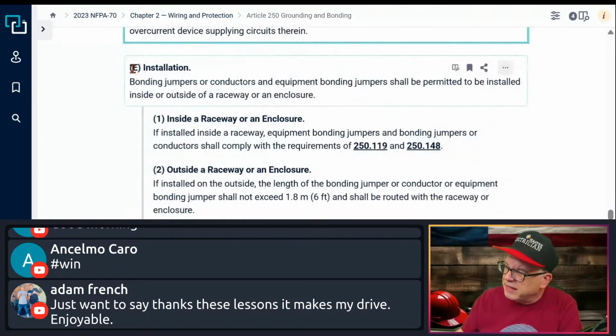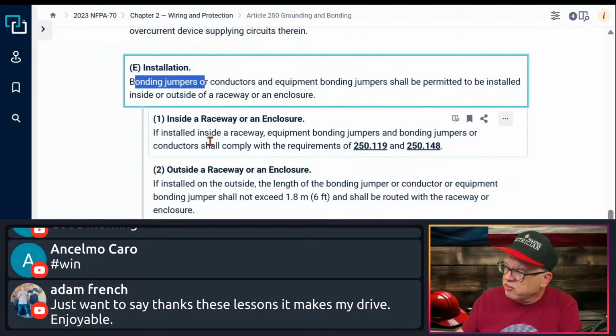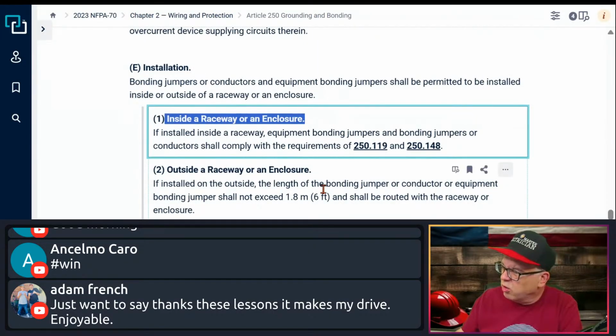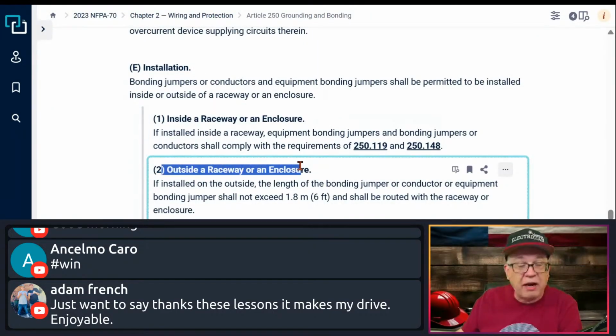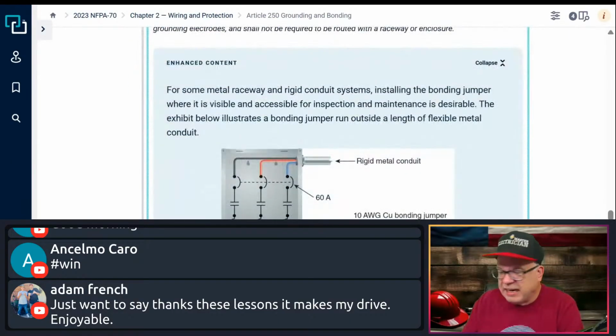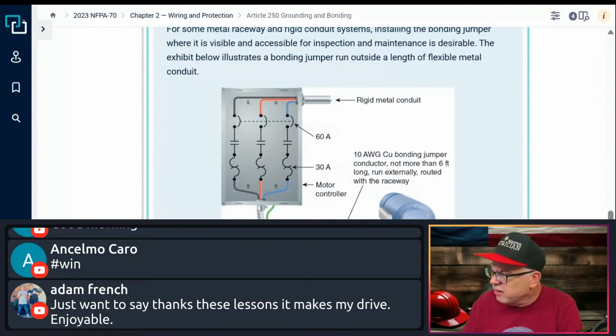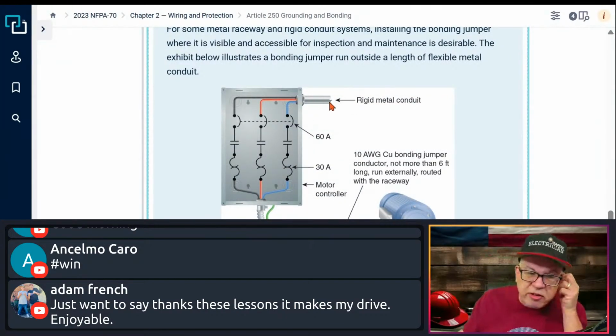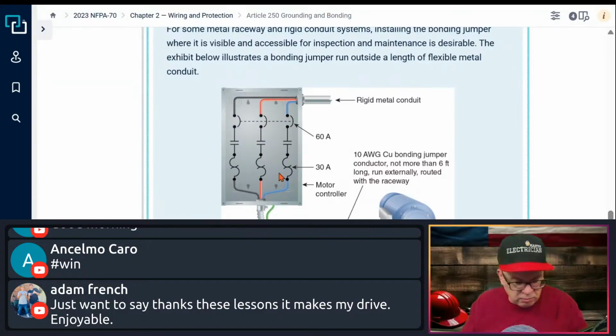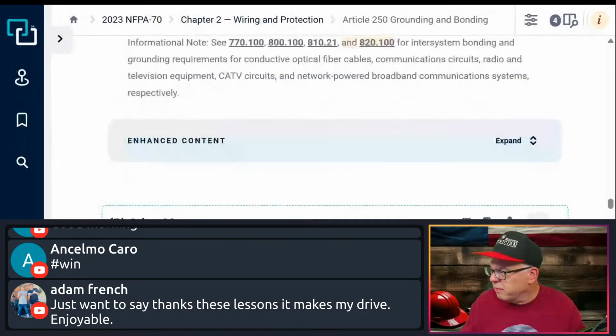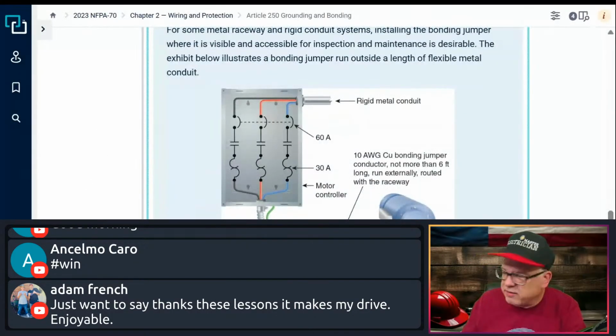But here we're talking about the installation of the bonding jumpers. So it can either be in the raceway or enclosure, or it can be outside. Now, if it's outside, okay, and I don't know if we have an example, is right here. So here's an example right here. Okay, so rigid's coming in. So this rigid is being used, obviously, in this example as the equipment ground, right? And I'll blow this up so you can see a little bit better, if it lets me blow it up. It's about as best that it's going to do.